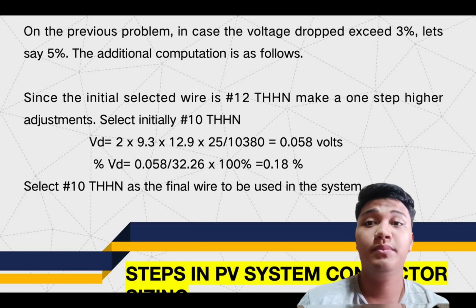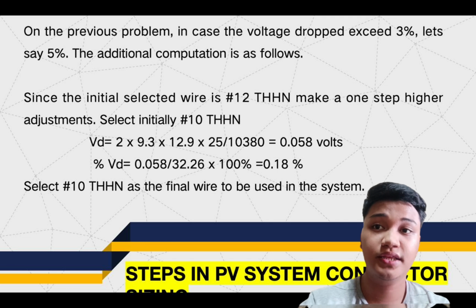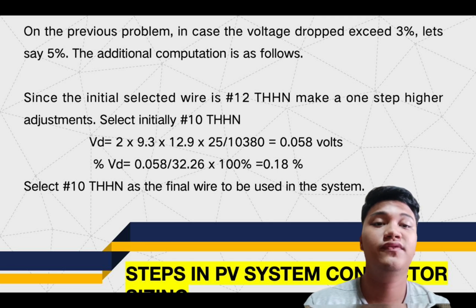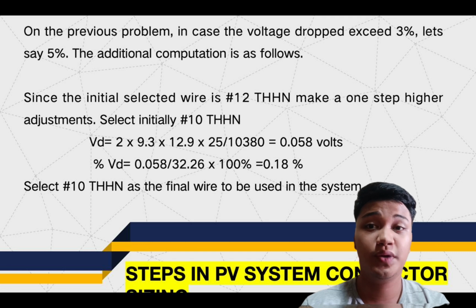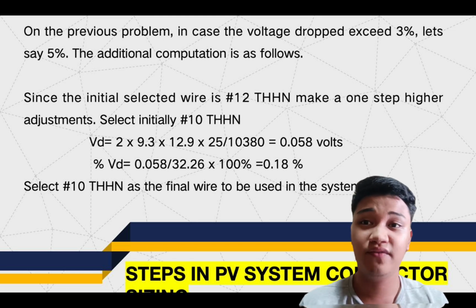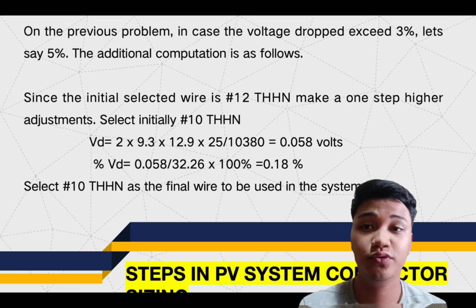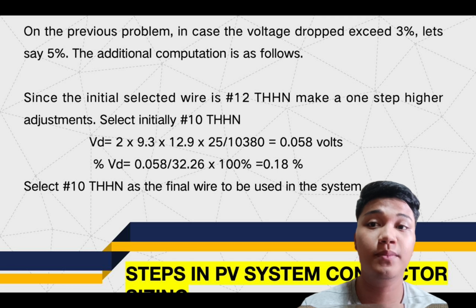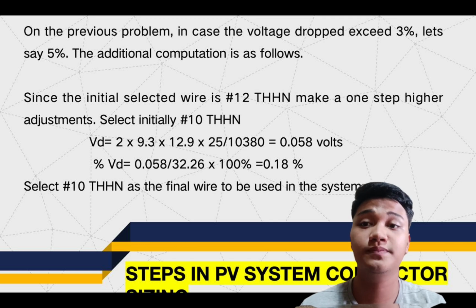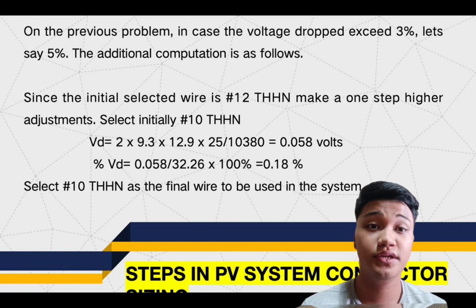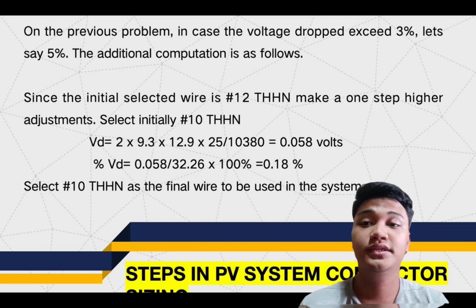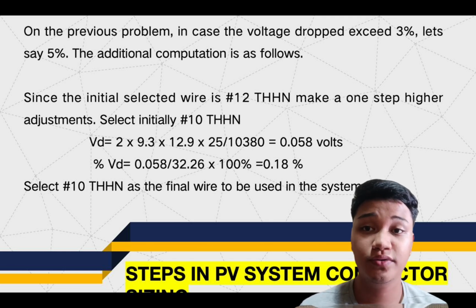On the previous problem, in case the voltage drop exceeds 3%, let's say 5%, the additional computation is as follows. Since the initial selected wire is number 12 THHN, make a one-step higher adjustment. Voltage drop is 2 times 9.3 times 12.9 times 25 all over 10,380 is equals to 0.058 volts. Ngayon, ang percentage voltage drop natin is 0.058 over 32.26 times 100% is equals to 0.18%. Select number 10 THHN as the final wire to be used in the system.